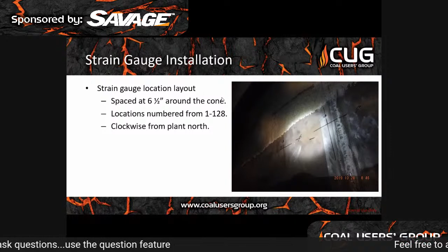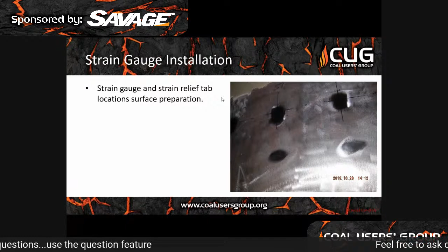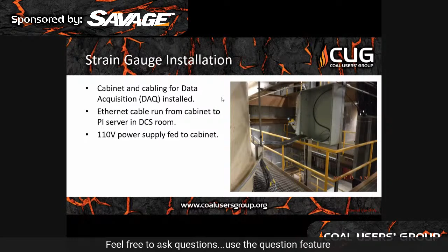We did the numbering, as Mark mentioned, 1 to 128. We started at azimuth 0 degrees, which was plant north on the silo, and installed the gauges clockwise around the cone. This is what it looks like when the locations get the surface prepped, ground down to get a nice flat metal surface. And this is on the outside, right above the cone, right at the interface of the cone and the shell, where the data acquisition controller was installed. We ran an Ethernet cable from this panel to the PI server in the DCS room, and powered it with a 110 volt feed.